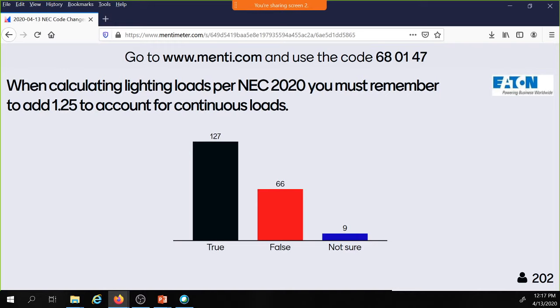So when calculating lighting loads per NEC 2020, you must remember to add 1.25 to account for continuous loads. Now, if I would have said NEC 2017, I would probably have said, yes, that would be a true. But the 2020 code made a recent change, and that is one of the first things we're going to hit out of the chute, that we built the 1.25 into Table 220.12. So stay tuned. Those 66 went to the code book probably and found that answer. And those 9 not sures, thank you for being honest. And those 70 are now, I mean, they heard the answer and they're jumping on that bandwagon. That's just the horse races. So in any case, the right answer to this one is false.